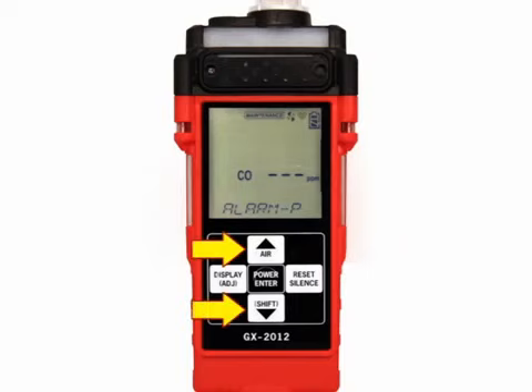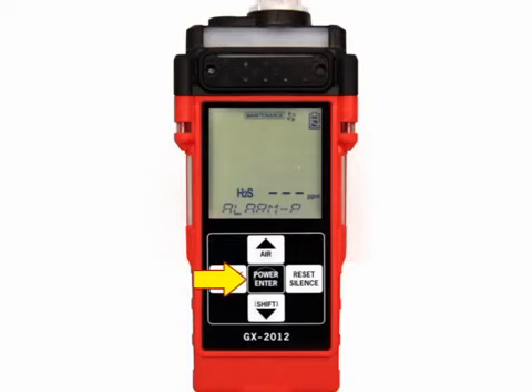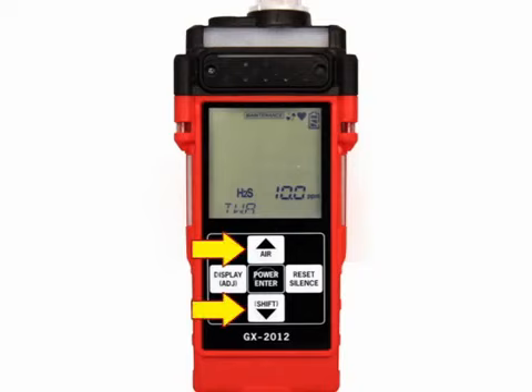Use the Air or Shift buttons to select the H2S channel in the alarm point screen and press Power Enter. Adjust the values for the warning and alarm settings. When you press Power Enter after selecting the alarm value, you will then be prompted to select the STEL value as you were with the CO channel. Use the Air or Shift buttons to change the setting and press Power Enter when finished. You will then be asked to enter a TWA value. Use the Air or Shift buttons to change the setting and press Power Enter when finished to return to the alarm point screen.